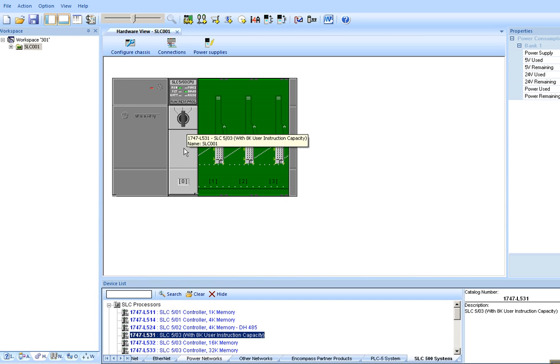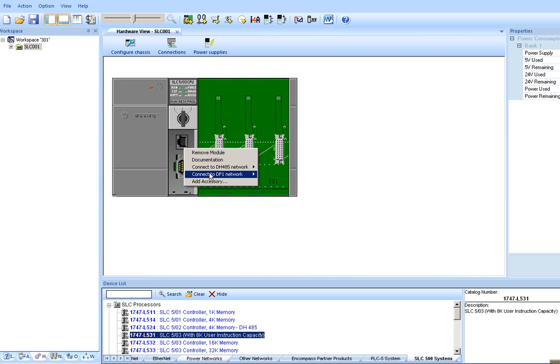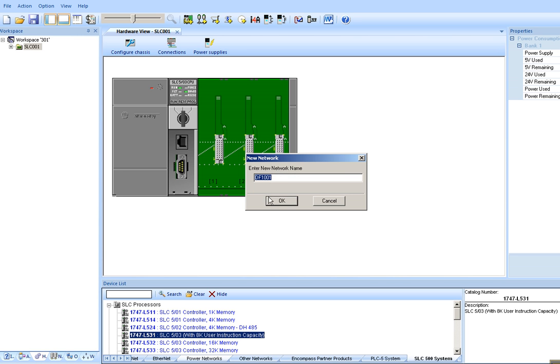Ensure that you select a processor that offers the 9-pin onboard serial port. Once selected, we can connect it to a DF1 network. The default name would be DF1001.